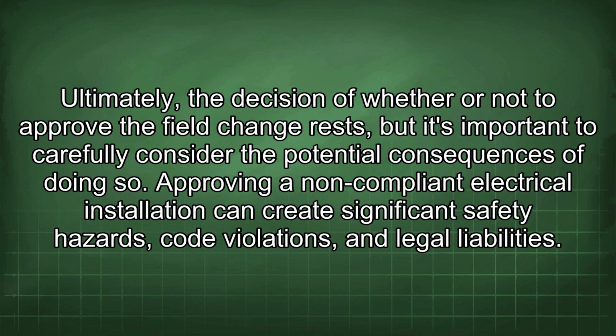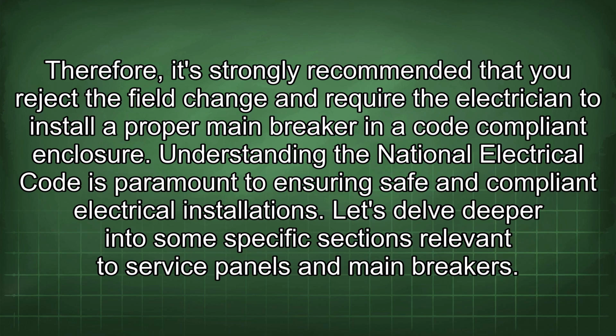Approving a non-compliant electrical installation can create significant safety hazards, code violations, and legal liabilities. Therefore, it's strongly recommended that you reject the field change and require the electrician to install a proper main breaker in a code-compliant enclosure. Understanding the National Electrical Code is paramount to ensuring safe and compliant electrical installations.